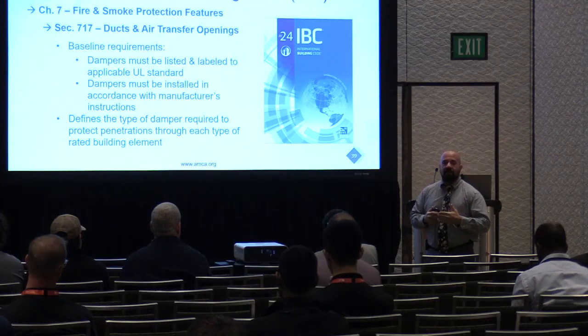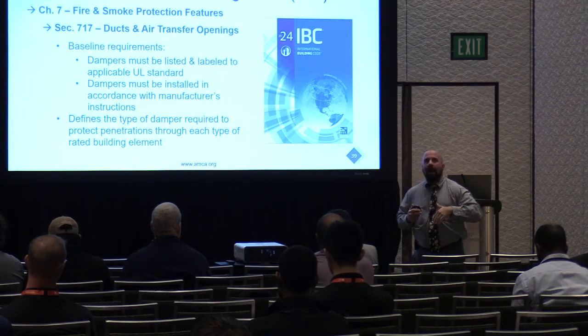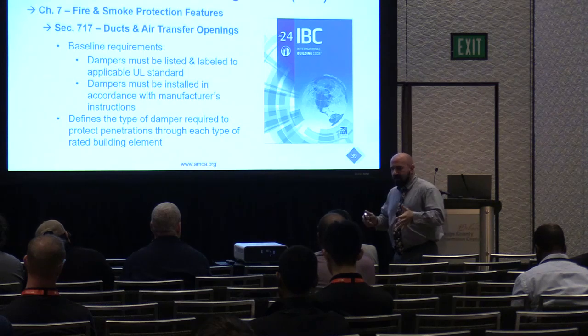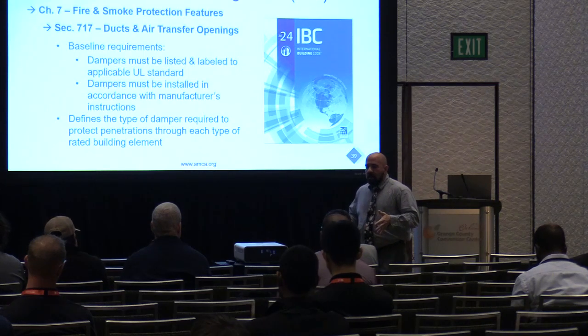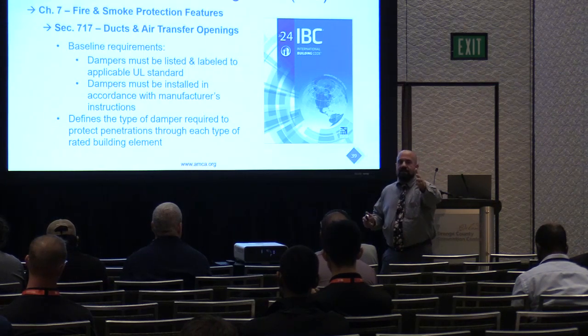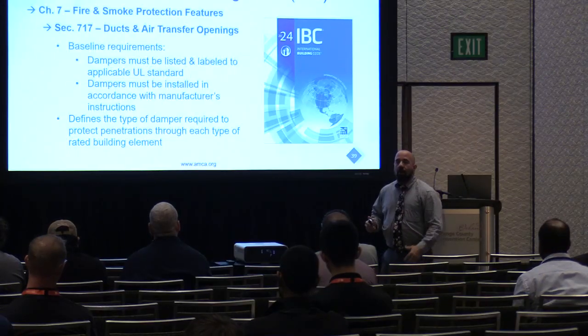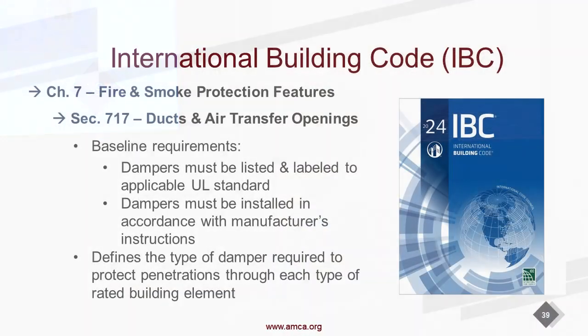But if you have something that is a little outside the scope of the manufacturer's installation details, I tell my contractors, call before you install. For my designers, call before you design. Talk to your damper manufacturers. Maybe there's a special product, or maybe there's a standard product. We want to make sure that we're building buildings safe in accordance with the code, but more importantly, we're installing them properly.